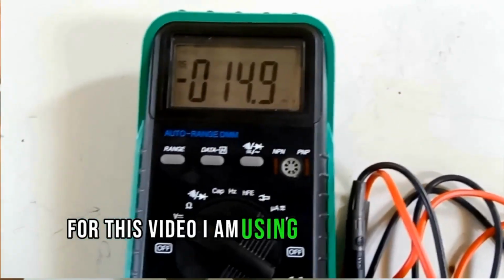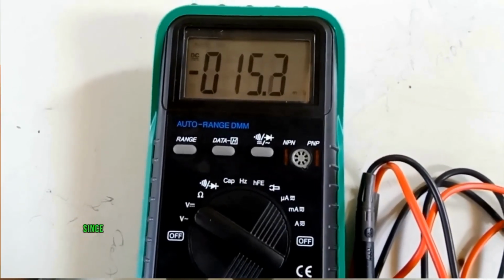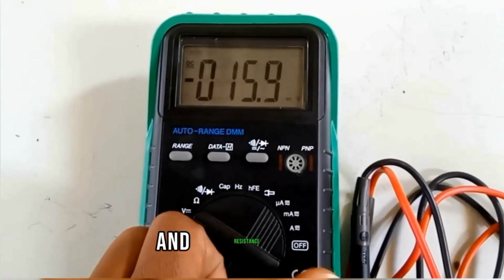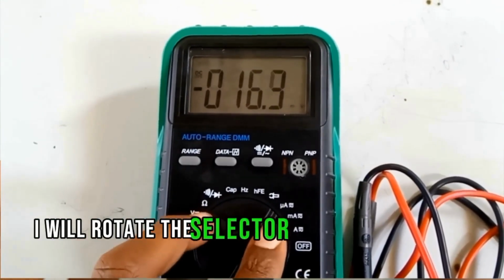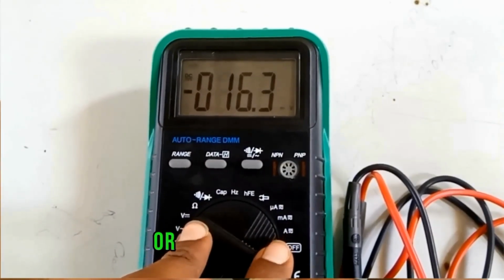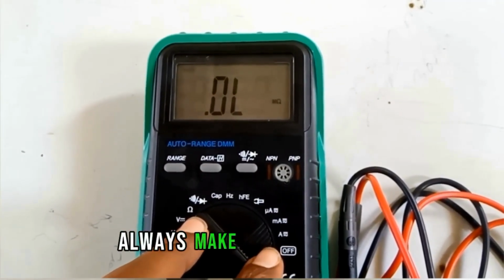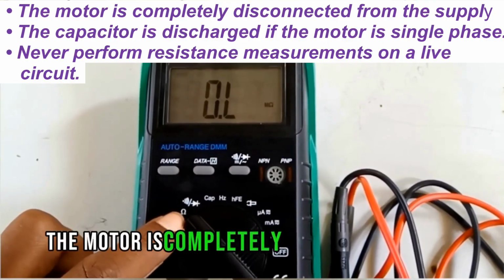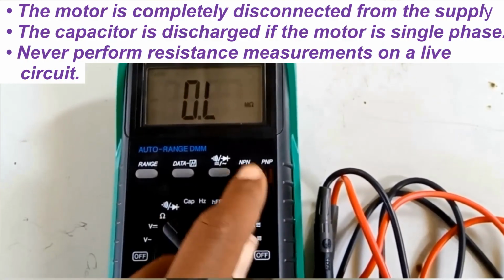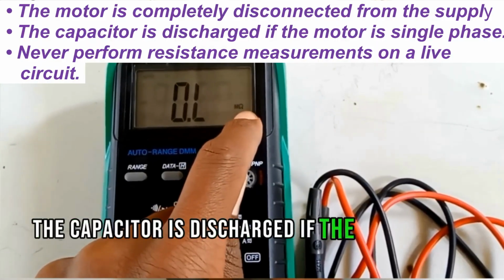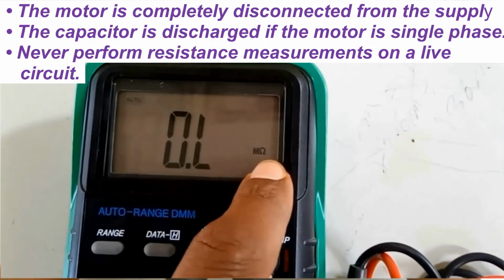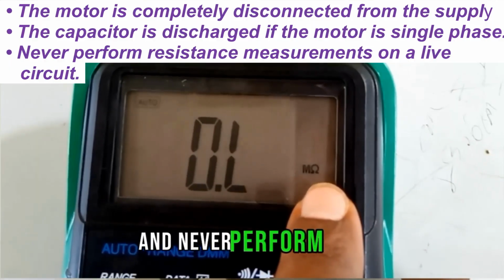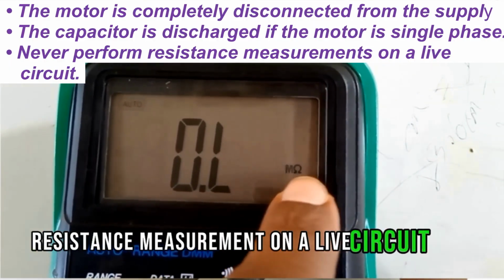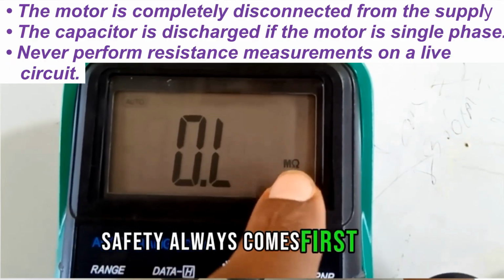For this video, I am using a digital multimeter. Since we are checking electrical continuity and resistance, I will rotate the selector switch to the resistance or ohm position. Always make sure that the motor is completely disconnected from the power supply. The capacitor is discharged if the motor has one, or is a single phase. And never perform resistance measurement on a live circuit. Safety always comes first.